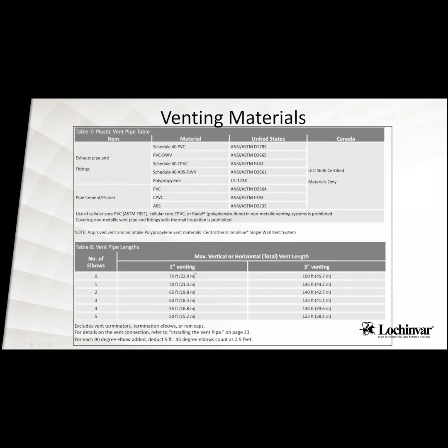For the venting, we're 2-inch on 75 feet, 3-inch 150 feet. For every 90 that you add, you subtract 5 feet. And for every 45, you subtract 2.5 feet on those.